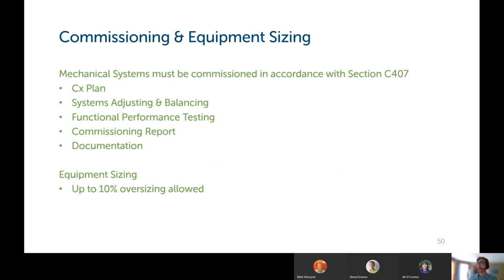Commissioning and equipment sizing. Mechanical systems need to be commissioned in accordance with Section C407, which I will go into details on later. That includes a commissioning plan, system adjusting and balancing, performance testing, commissioning report, and some documentation. There's a note in here that equipment can only be oversized 10% in this code.